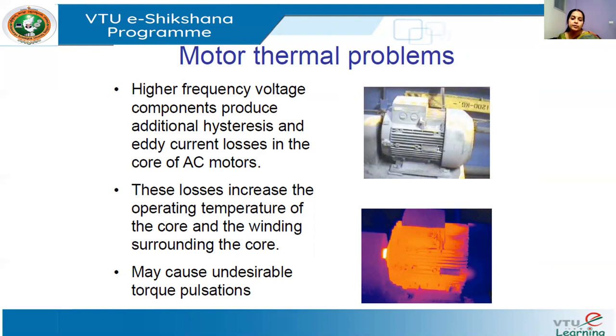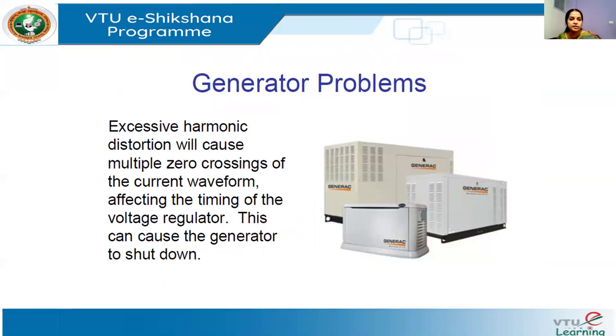Generators also have problems with harmonics. You have a voltage regulator to control the generator voltage. With harmonics — fundamental, third, fifth harmonics, each at higher frequencies — there are many zero crossings. These are not the actual zero crossings of the main waveform; the harmonics cause multiple false zero crossings in the current waveform, which affects the timing of the voltage regulator. This will cause shutting down of the generator.